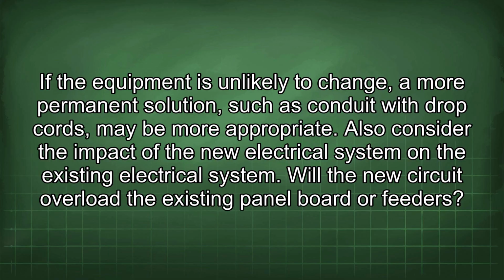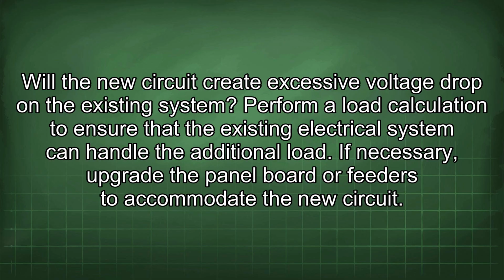Also consider the impact of the new electrical system on the existing electrical system. Will the new circuit overload the existing panel board or feeders? Will the new circuit create excessive voltage drop on the existing system? Perform a load calculation to ensure that the existing electrical system can handle the additional load. If necessary, upgrade the panel board or feeders to accommodate the new circuit.